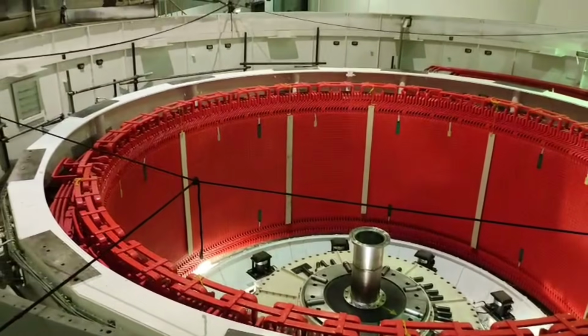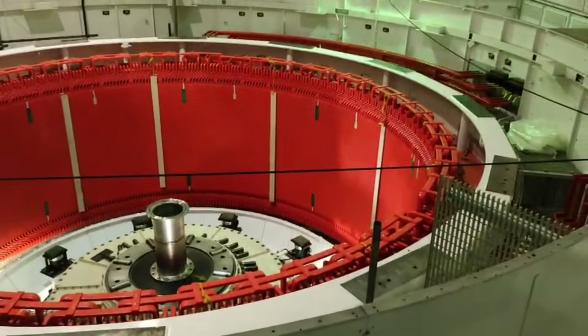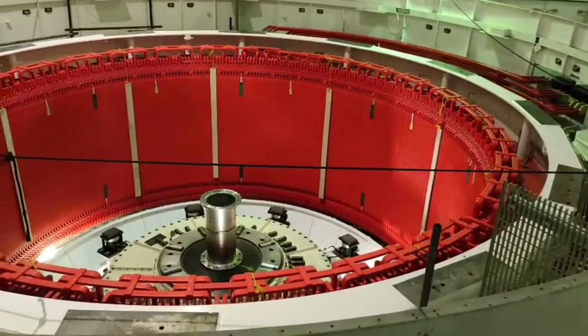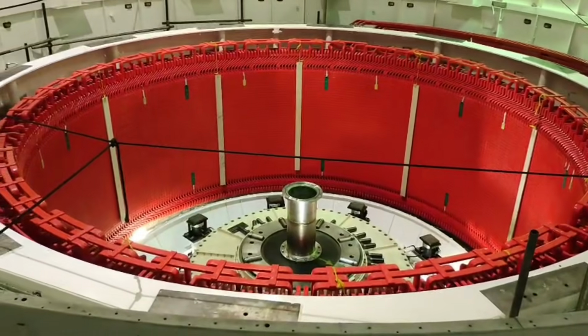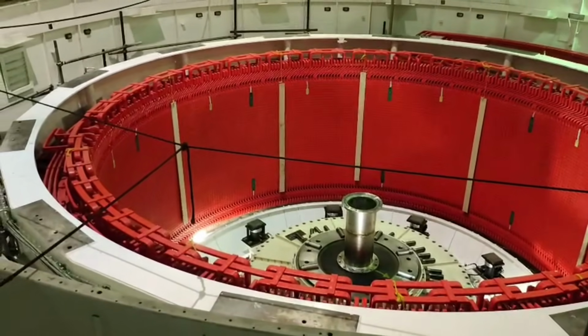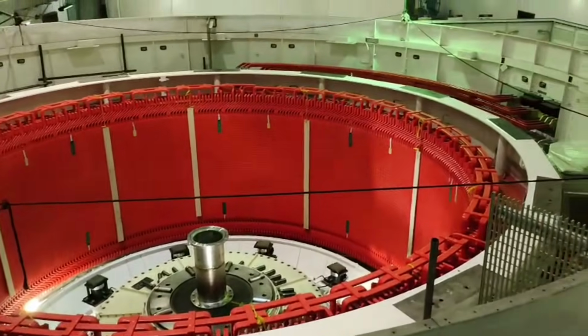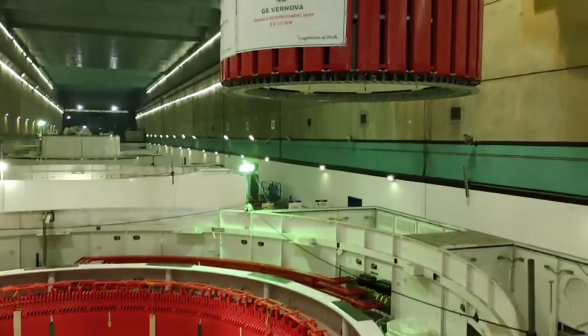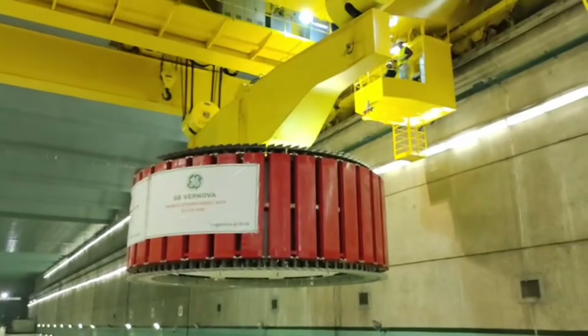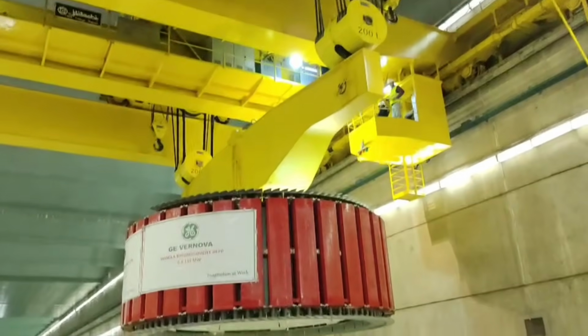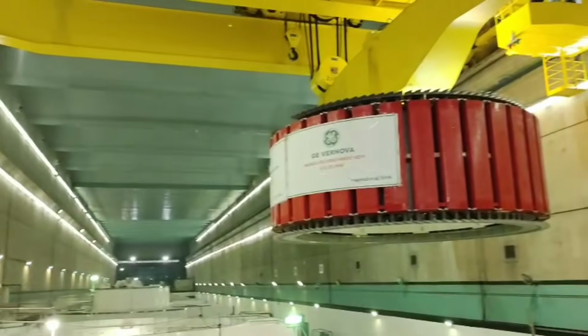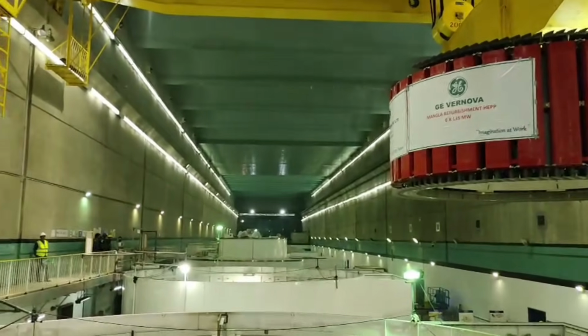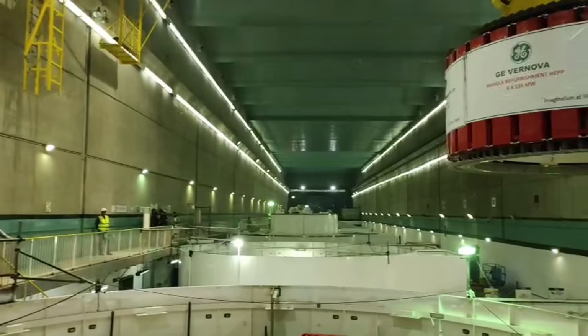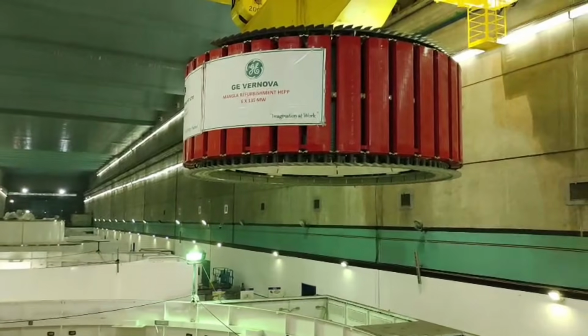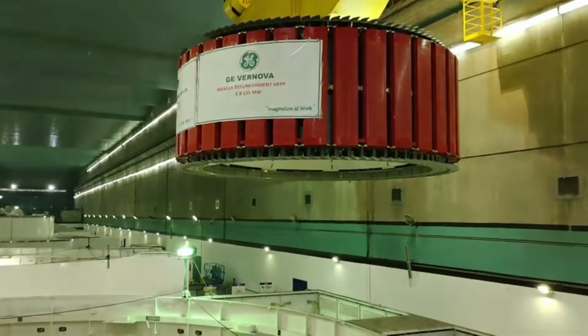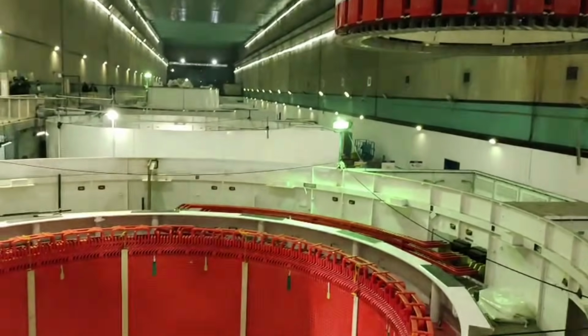So the next time you see a giant hydro generator spinning deep inside a powerhouse, remember this: the turbine may provide the force, but the excitation system is what gives the machine electrical life. It creates the magnetic field, feeds current into the spinning rotor through carbon brushes and exciter ring, controls voltage, stabilizes the grid, protects the generator, and silently reacts to disturbances every single second. Without it, modern power systems simply would not work. And the crazy part is most people stand inside a powerhouse, never even realize this hidden system exists.